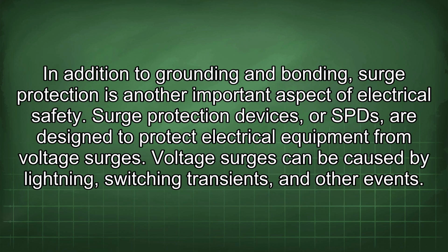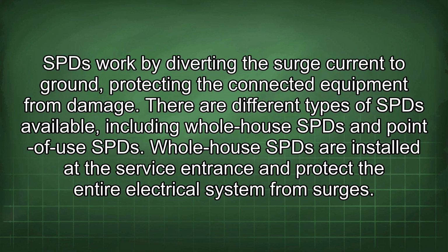In addition to grounding and bonding, surge protection is another important aspect of electrical safety. Surge protection devices, or SPDs, are designed to protect electrical equipment from voltage surges. Voltage surges can be caused by lightning, switching transients, and other events. SPDs work by diverting the surge current to ground, protecting the connected equipment from damage.